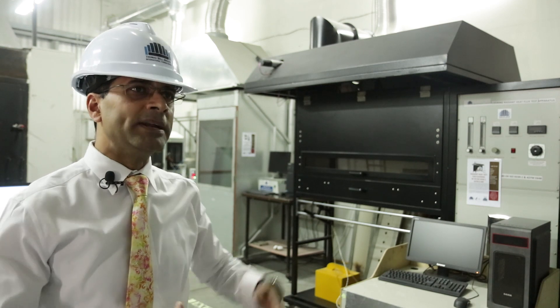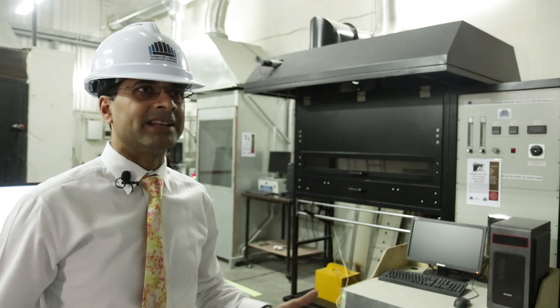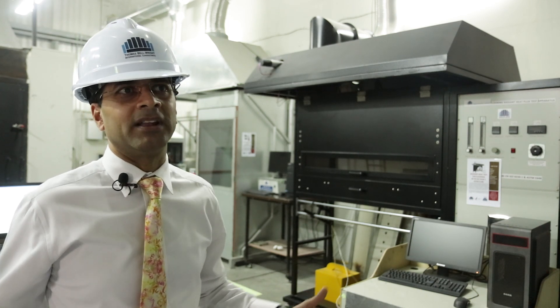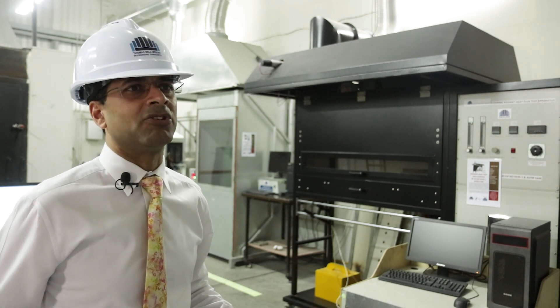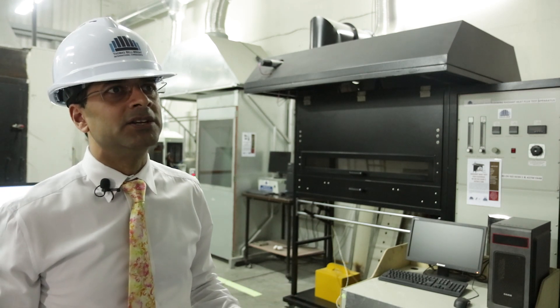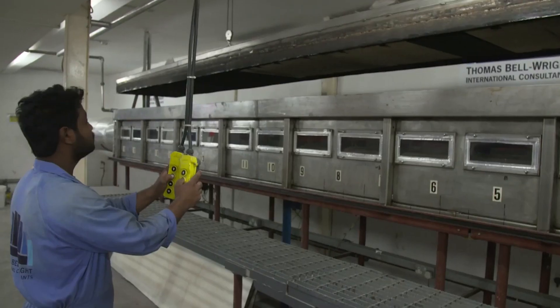This is our reaction to fire lab. We used to run only the ASTM E84, which is the American standard tunnel test, but we have now added the complete Euro Classes classification tests. These are mandated in the UAE fire and life safety code and are important for classifying cladding material, flooring material, and interior finishing material. The classification standard is the EN13501-1, and it uses data from several equipment types — a calorimeter, a single flame source test, and a single burning item test — to assess ignitability, combustibility, flame spread, and droplet behavior.